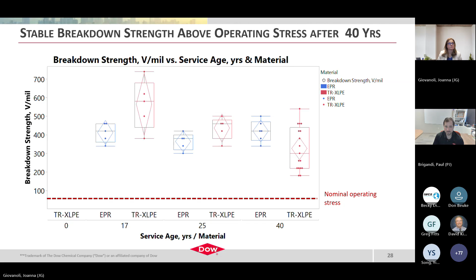One of the key things we'd like to highlight, particularly as we talk about data center integration and the drive to a more sustainable future and decarbonization, is that tree retardant XLPE materials have by far lower dielectric losses from a material standpoint. That means more efficient transfer of power from point A to point B where it's used, so we can maximize the amount of power that can be generated. The lower the dielectric loss number, the better, and you can see the significant difference when you compare the two types of materials. So tree retardant XLPE has good opportunity here as we talk about implementation and data center usage and builds.